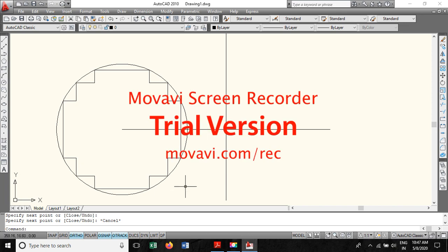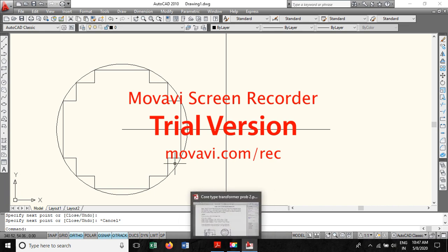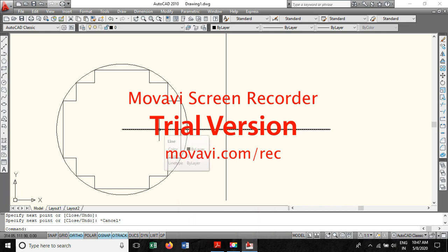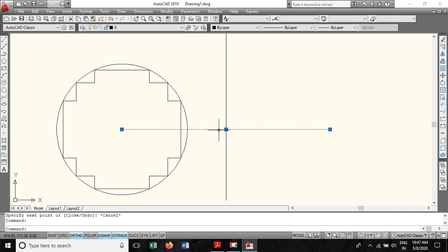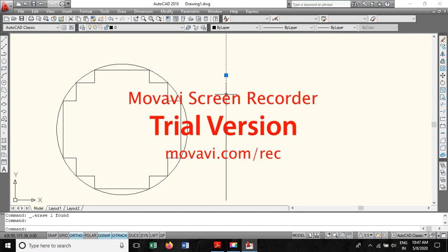So 155 will come somewhere here, it will not overlap. That is how I have to check whether the inner LV, outer LV, inner HV, outer HV diameters have been taken correctly. Okay. Check for the outer HV. That is an important thing, how to cross check.